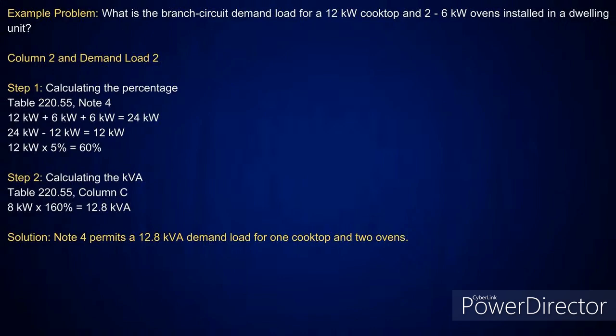I'm feeding all of this with one branch circuit, where the other one, they were 3 individuals. Okay? So since this is one circuit, I'm going to add it all together and subtract it by what? 12 again. That gives me 12 kW. That's your additional kilowatt for each one. That gives you 60%. So then I look at, because it's on one circuit, we're going to treat it as one range here. We're just going to come across, pick up the 8 kW at 160%, and that's going to give me 12.8 kVA or 12,800 VA.